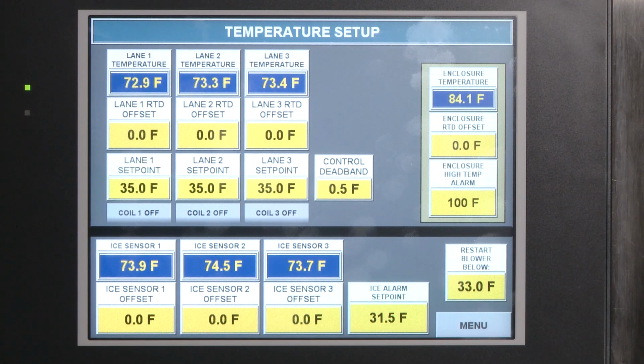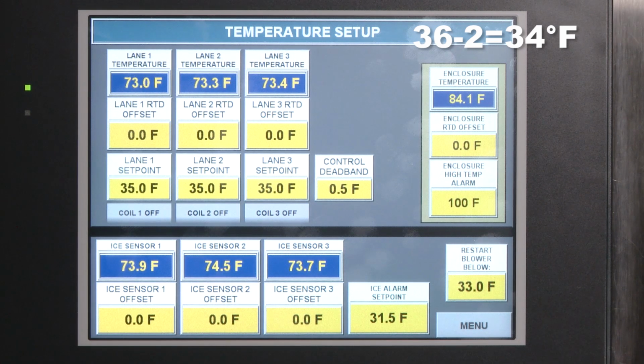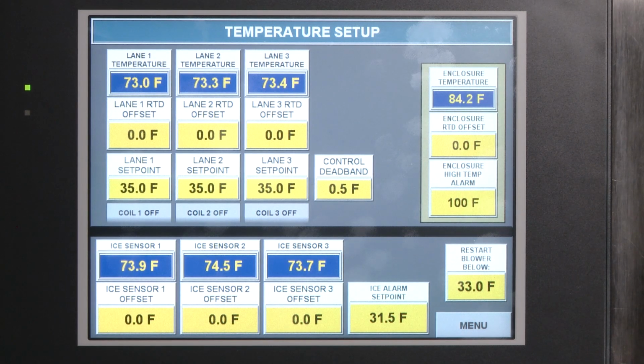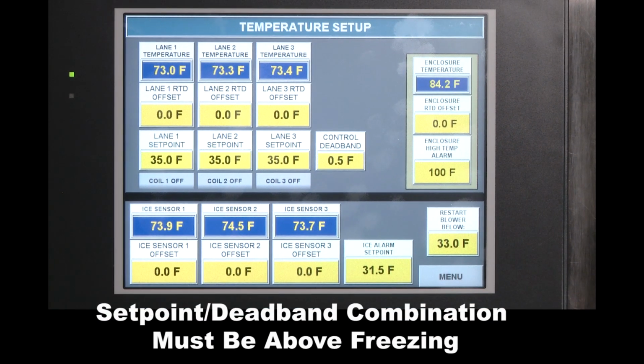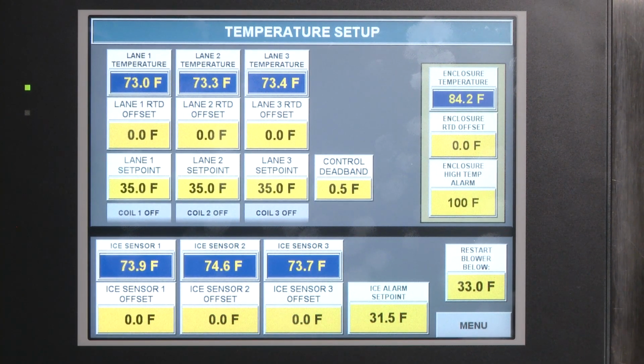For example, if the tank set point equals 36 degrees Fahrenheit, the tank deadband equals 2 degrees Fahrenheit. This means that refrigeration will turn on above 36 degrees Fahrenheit and off below 34 degrees Fahrenheit, 36 minus 2. Entering a set point deadband combination that gives a shutoff below freezing will automatically calculate a new set point. For example, if the set point is equal to 33 degrees Fahrenheit and the deadband is 4 degrees, the shutoff will be 29 degrees Fahrenheit, which is below freezing. The deadband will be added to a fixed value above freezing and change the set point.